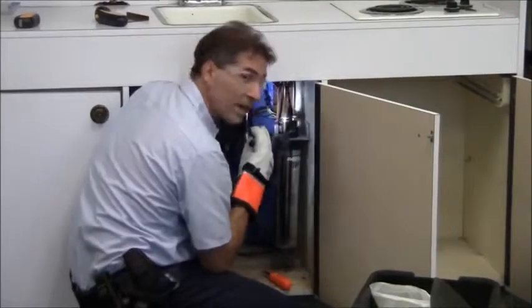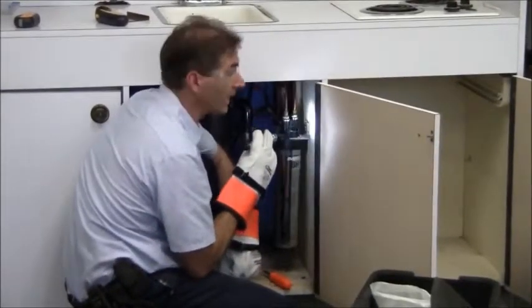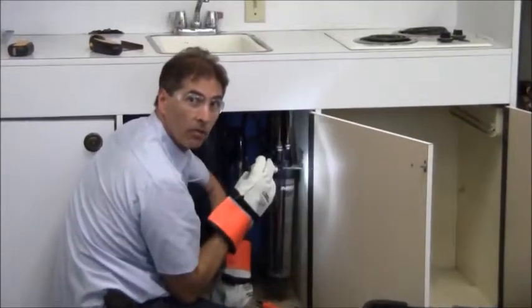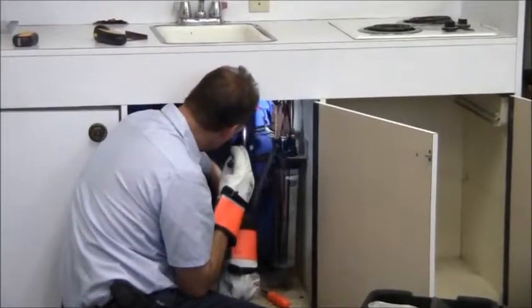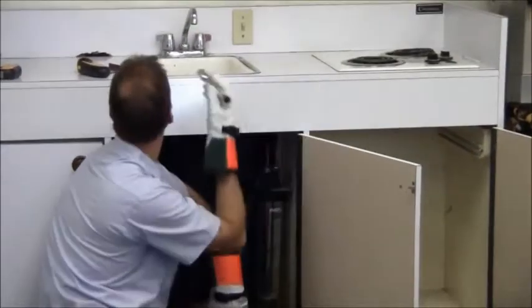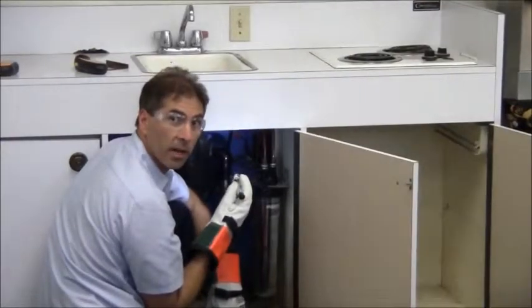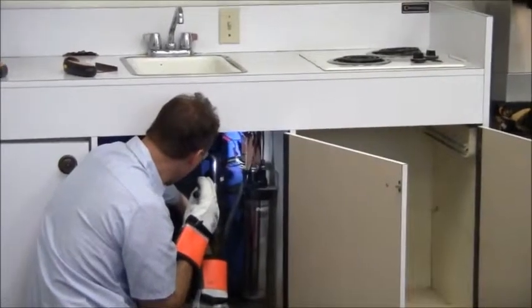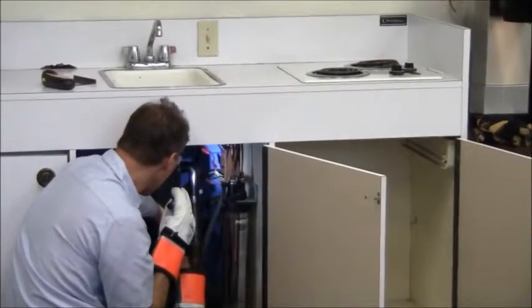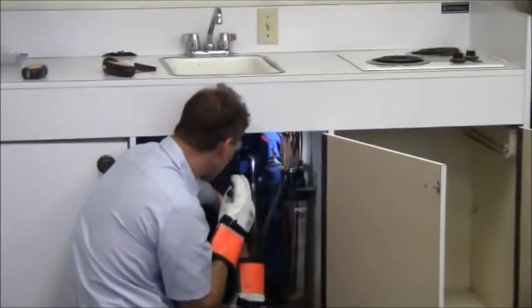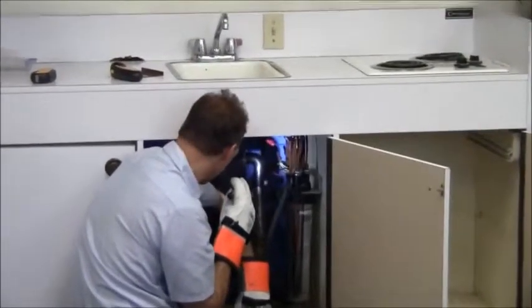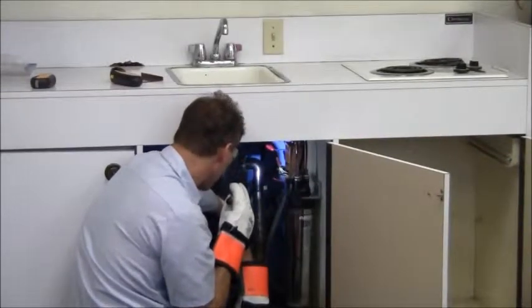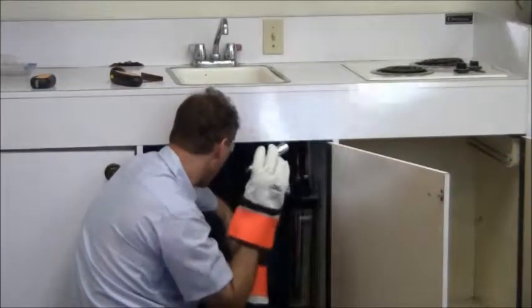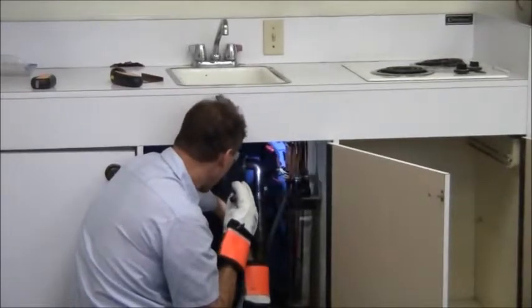There are three colors going up there: white, black, and green. So that must be 110 volts, which is good for me because this particular tracer works with 110 volts, not a higher voltage. So what I can do is throw on jumper cables from the neutral or even the ground to the hot, put my tracer on, and find this breaker without too many problems.